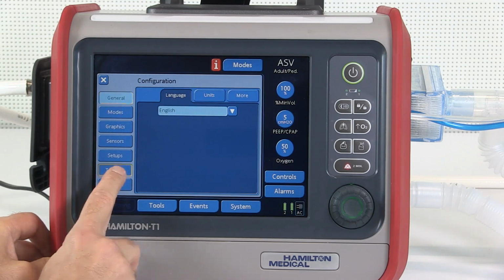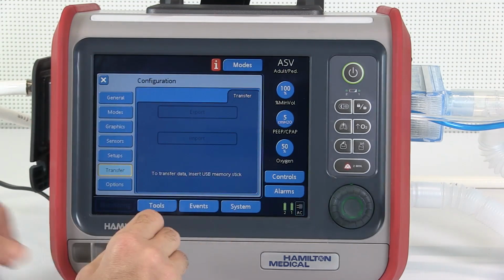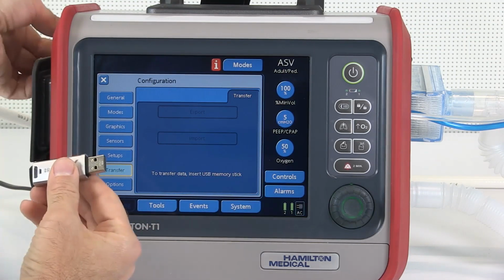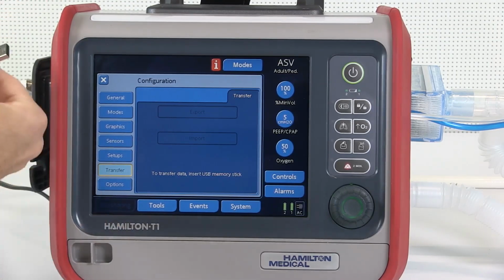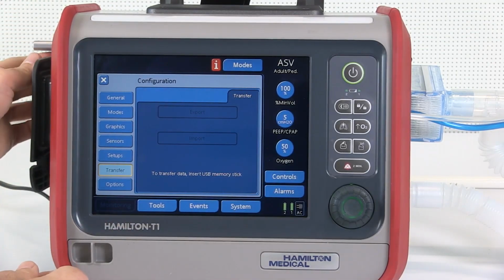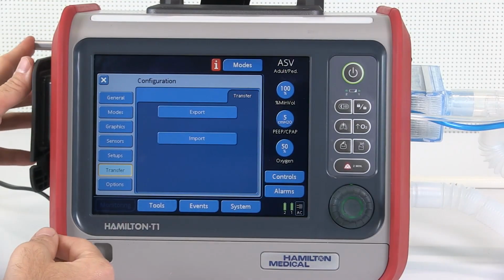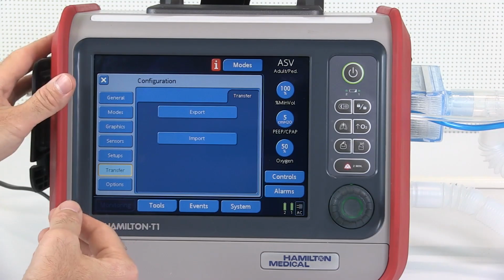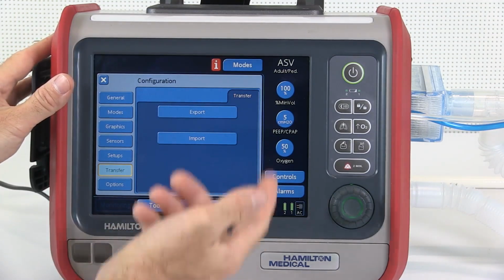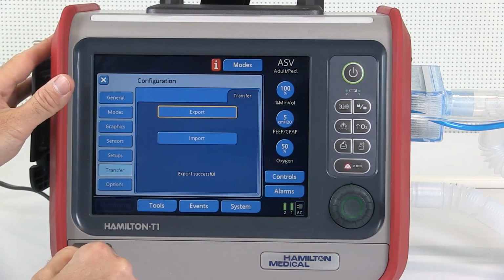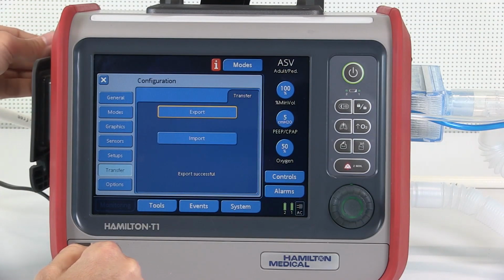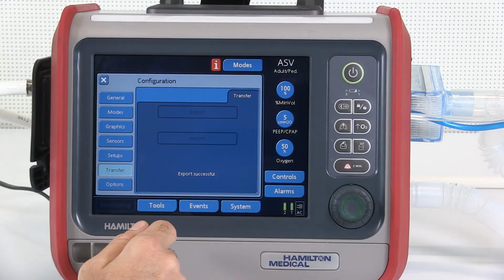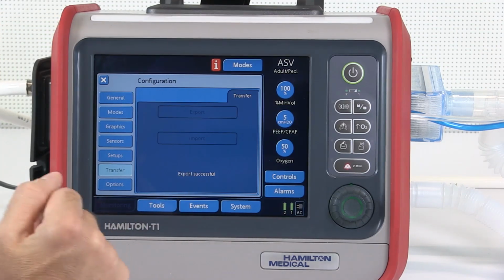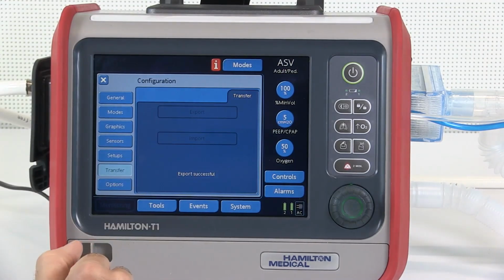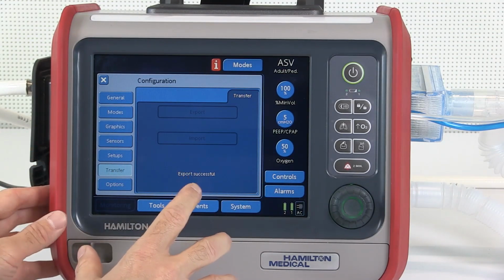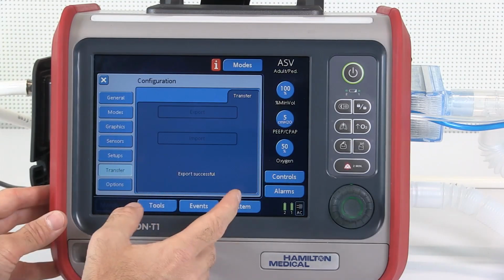Touch Transfer to export the configuration settings. Insert a USB flash drive into the USB port. Touch Export to export the configuration file, or Import to import a configuration file. The Configuration Import feature allows for convenient transfer of the configurations from one ventilator unit to another if the same configuration needs to be installed on several ventilators. The exported XML configuration files will be stored in a folder called Import-Export Config Files on the USB flash drive.